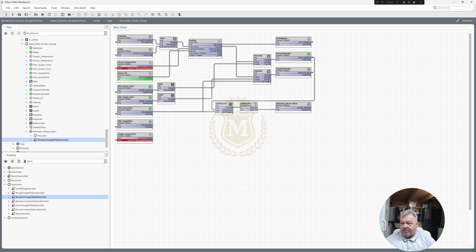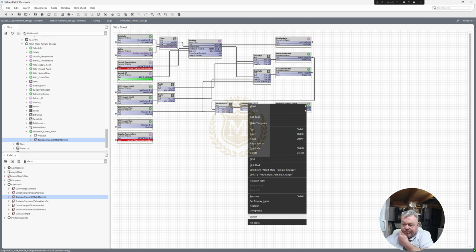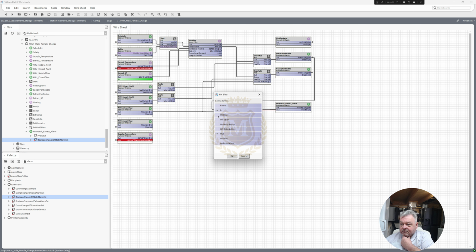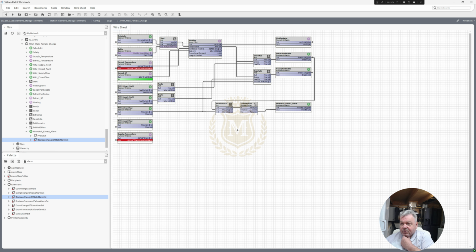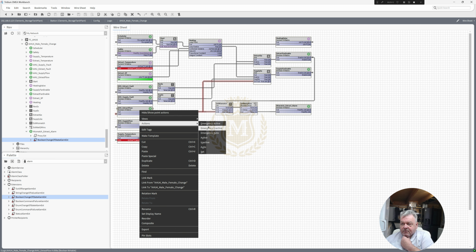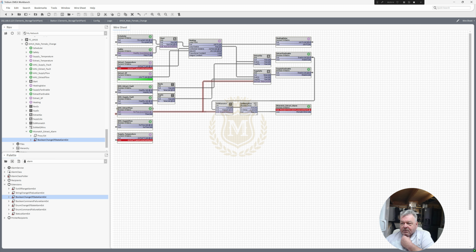So when we do get a mismatch alarm after 2 minutes, let's show the time in there on delay. Leave it at 1 second at the moment just to show you it working. And we'll take the flow off. And then you should get a mismatch alarm there.